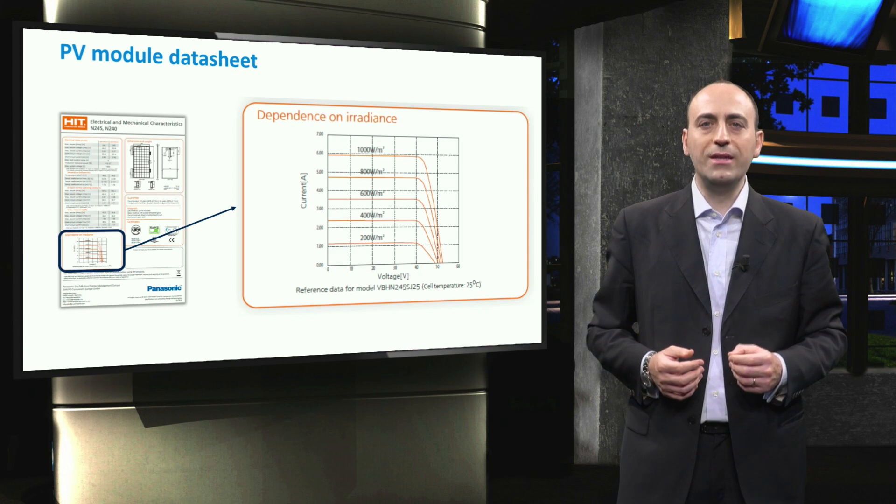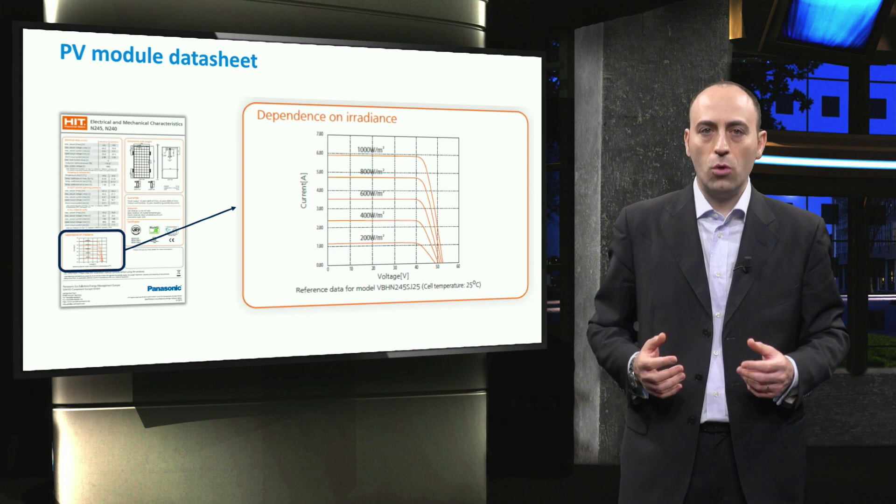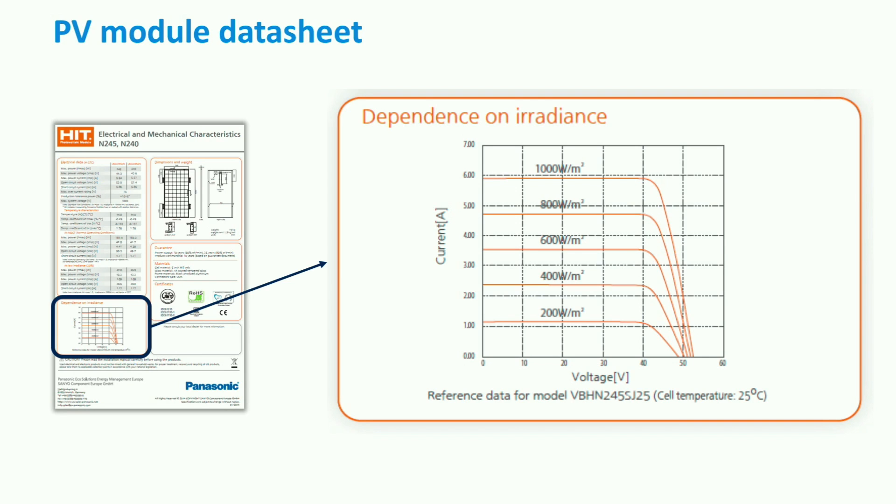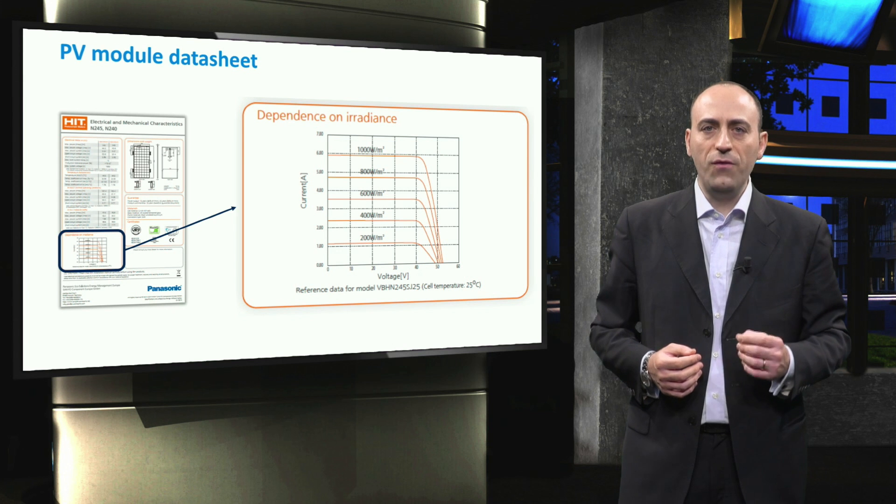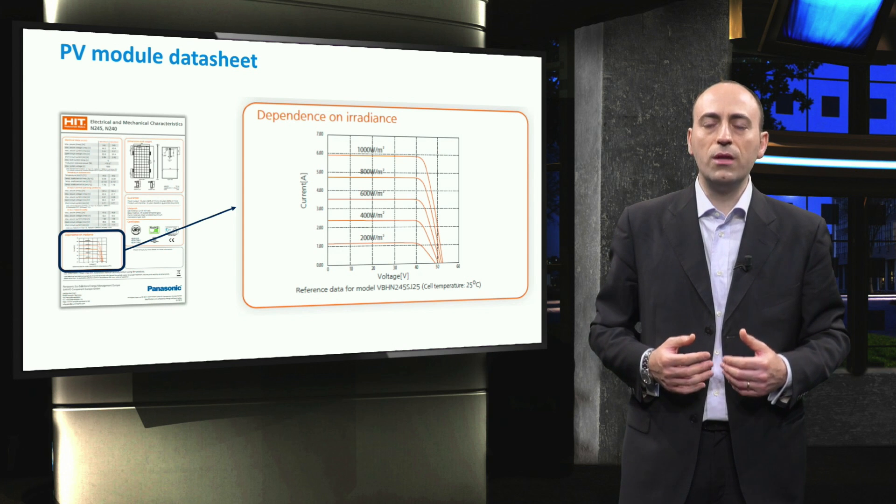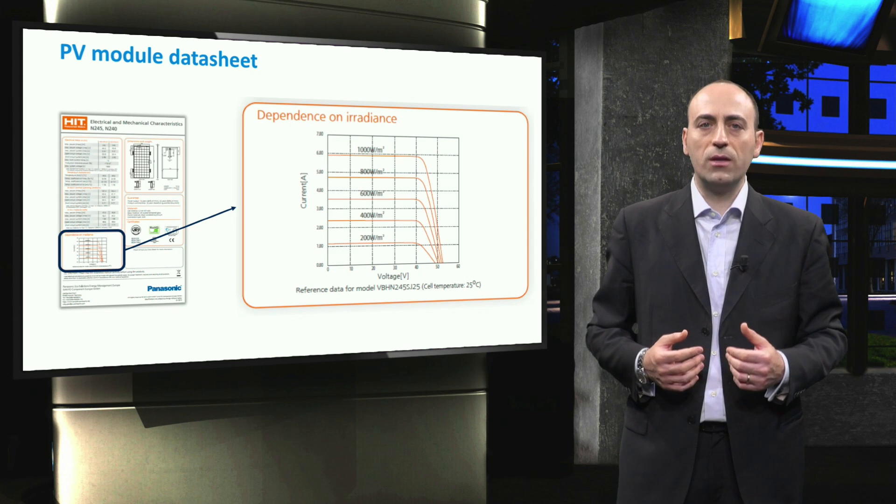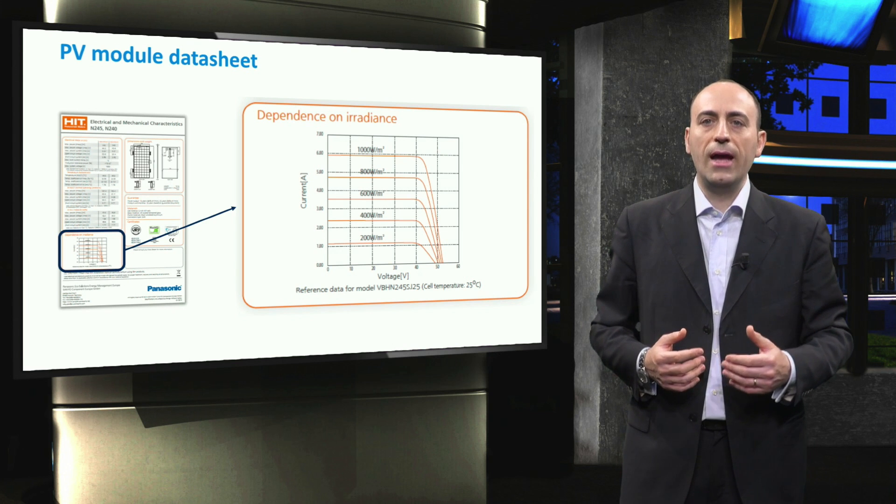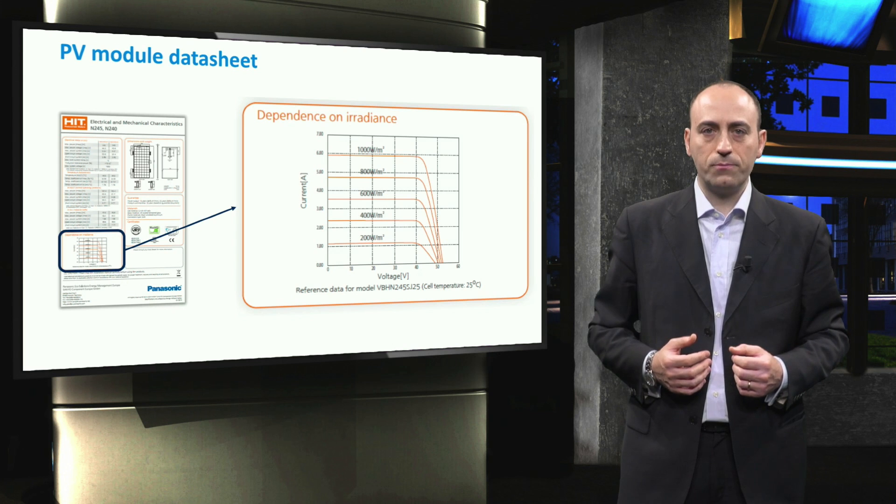Another important module parameter is the irradiance dependence of the module. These are the voltage-current characteristics under different irradiance conditions and at constant module temperature of 25 degrees Celsius. Generally, a single light source is used to simulate the different irradiance levels. The irradiance level is reduced through the use of filters. At a fixed temperature, the current increases with increasing irradiance, starting from more than 1A at 200 Watt per square meter to a value of 5 times higher at 1000 Watt per square meter.